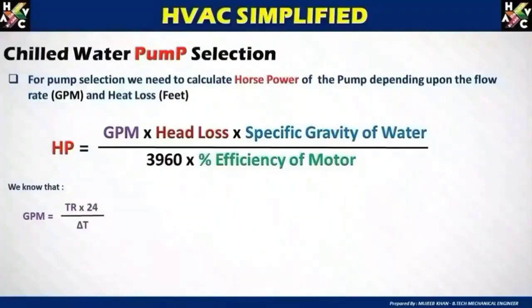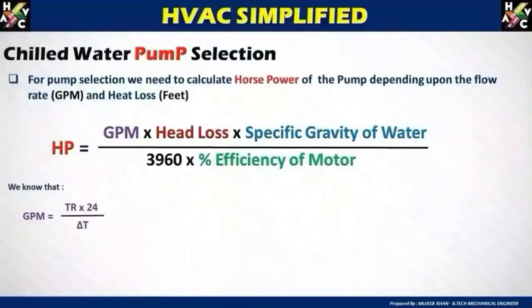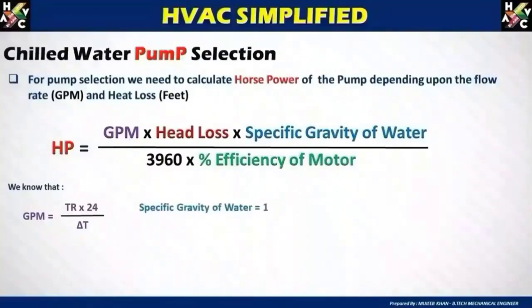GPM is equal to TR × 24 divided by delta T. I have made a separate video explaining the GPM calculation in detail, which will be linked in the description. You can refer to it to understand how to calculate GPM.